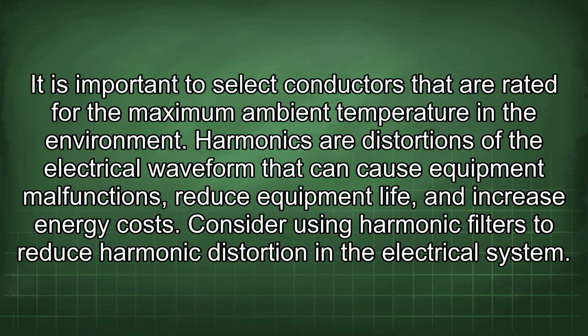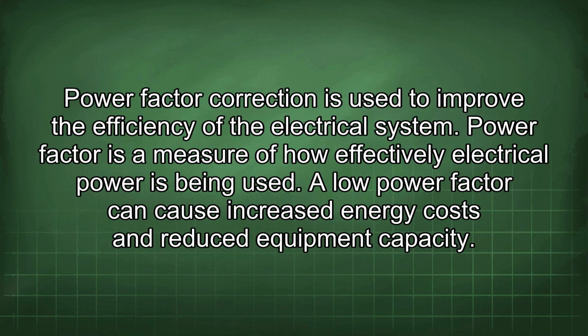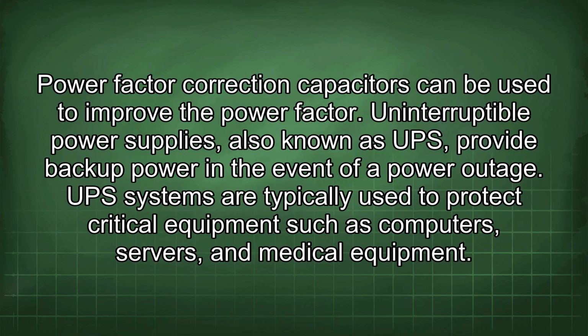Harmonics are distortions of the electrical waveform that can cause equipment malfunctions, reduce equipment life, and increase energy costs. Consider using harmonic filters to reduce harmonic distortion in the electrical system. Power factor correction is used to improve the efficiency of the electrical system. Power factor is a measure of how effectively electrical power is being used. A low power factor can cause increased energy costs and reduced equipment capacity. Power factor correction capacitors can be used to improve the power factor.